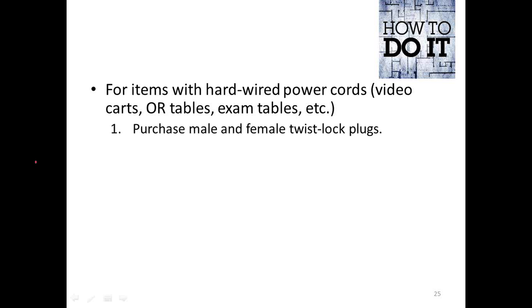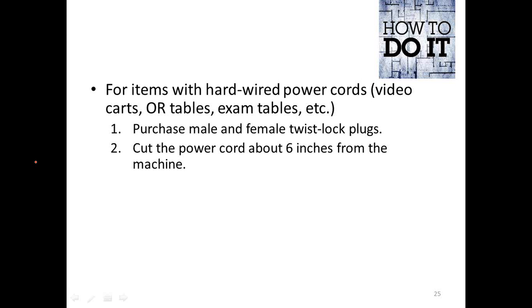Go out and buy some male and female twist lock plugs. They're 3-wire plugs, but they twist and lock together so you can't pull them out. Step 2: you take your piece of equipment, like a video cart, an OR table, or an exam table, and you cut off the existing power cord about 6 inches from the machine.